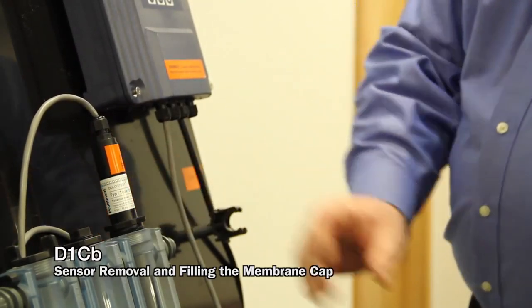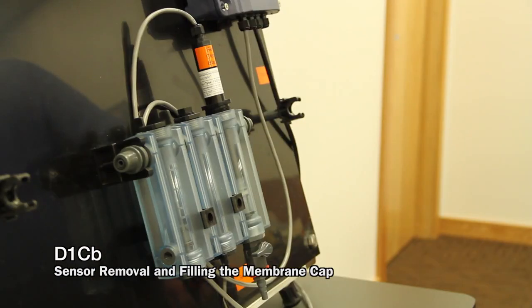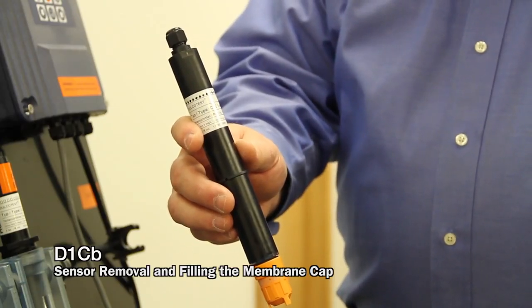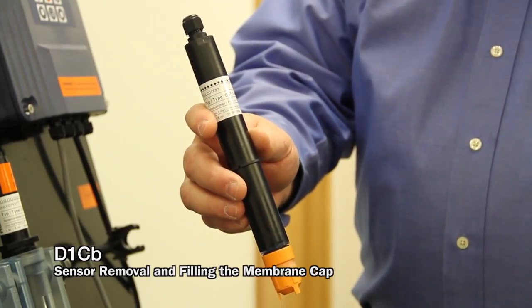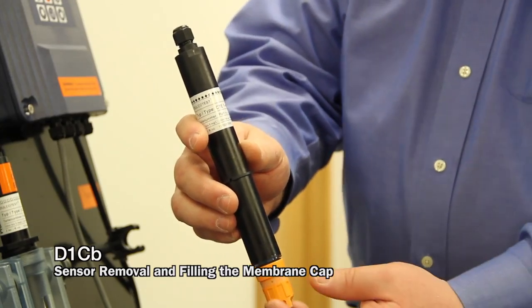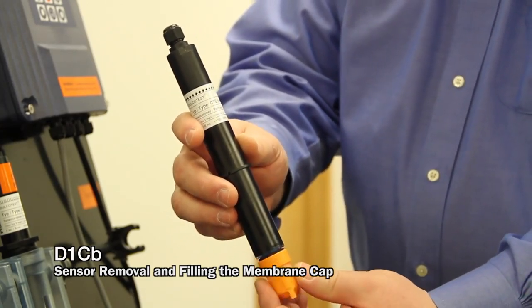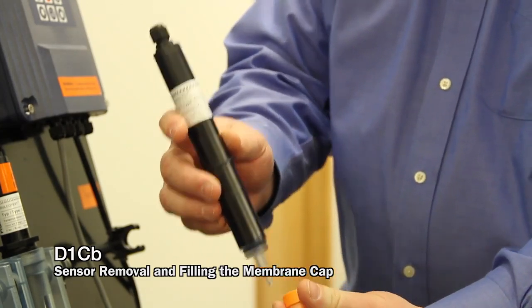We can now start flow in the sample line after we've changed the electrolyte, or if we've first installed the electrolyte. It takes several hours to get a true reading before we want to do our calibration. Some of our sensors have electrolyte that is a little bit more viscous, so to change or to add the electrolyte in that, again, we're going to remove that cap.